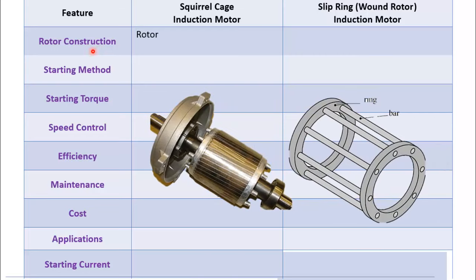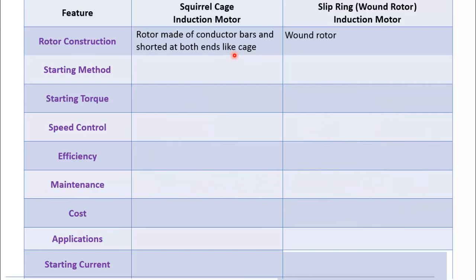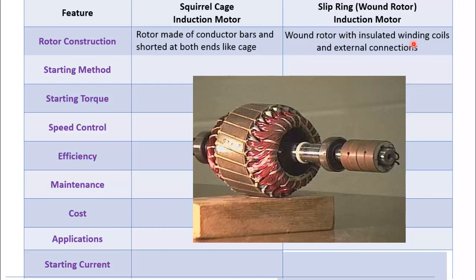Construction wise, squirrel cage motor has a rotor made of a cylindrical core with conductive bars. The bars are shorted at both ends by end rings, resembling a squirrel cage. Slip ring motor has insulated windings with slip rings and brushes for external connections.